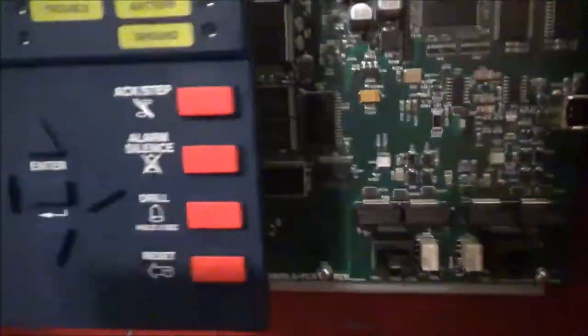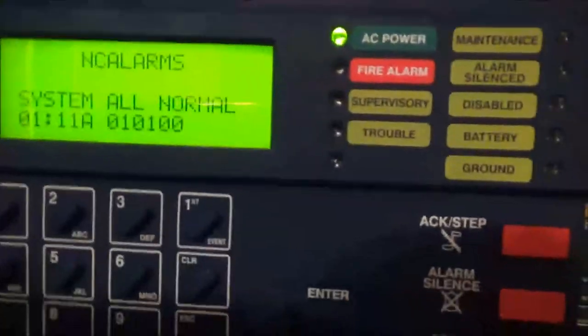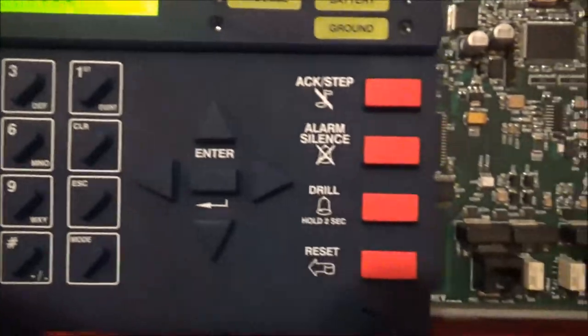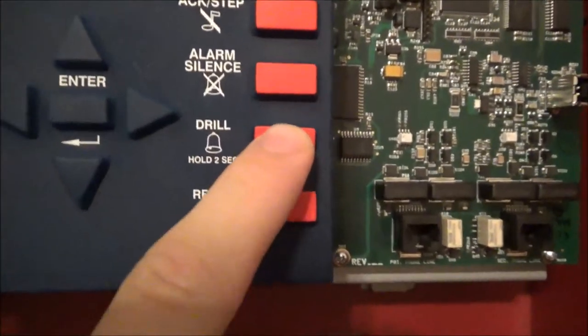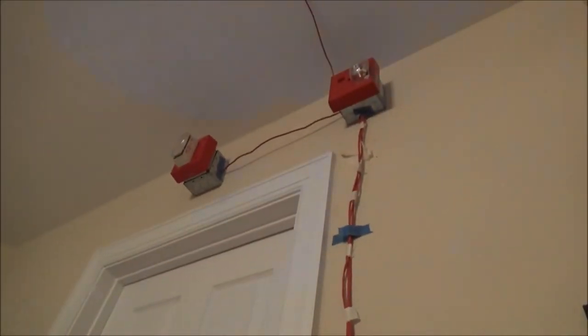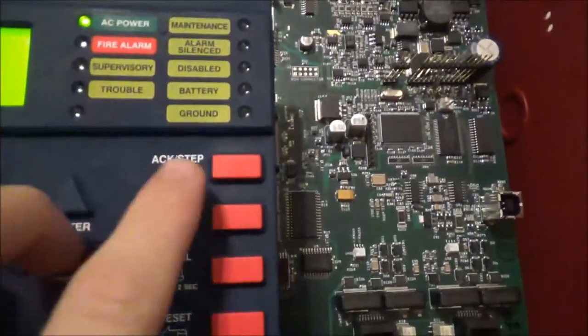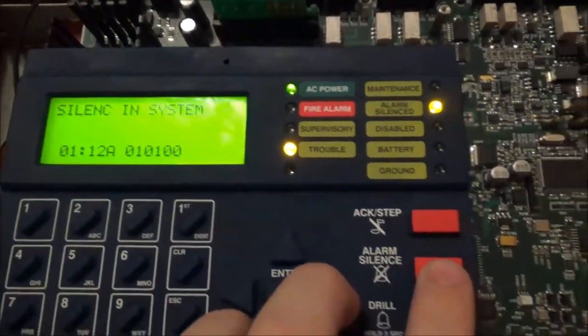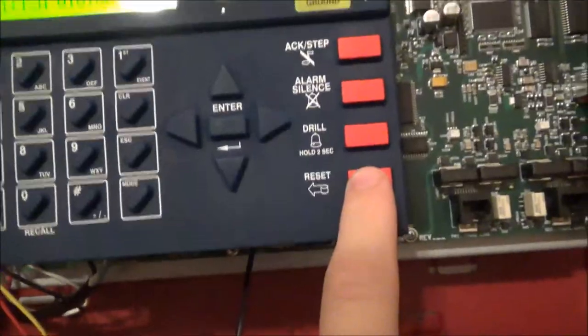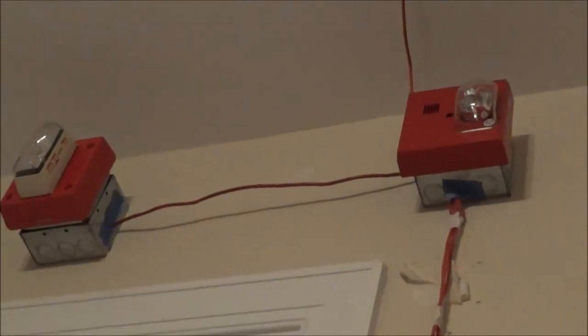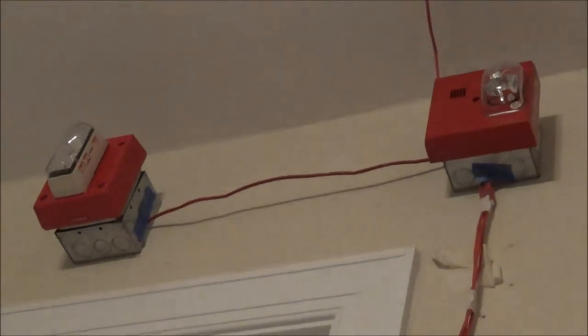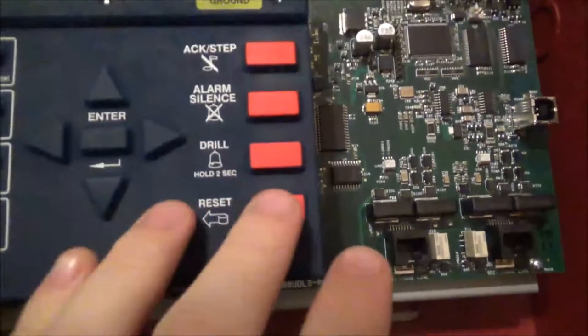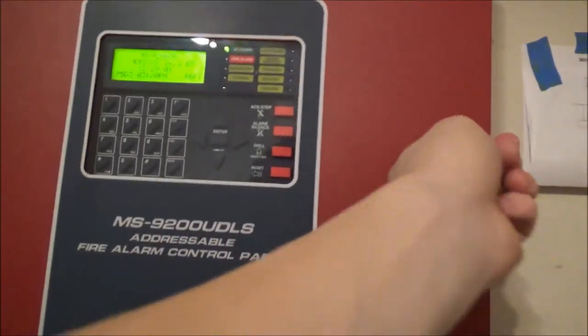The last thing we're gonna do, we are going to do a fire drill. Let's call monitoring. Actually, let's not because I don't have monitoring, but here we go, three two one. Silenced. Building's clear, so we get some strobe action in this video. Alright. And reset for the last time today.